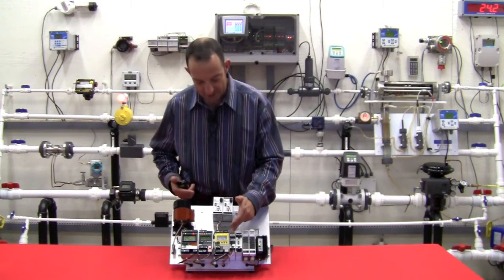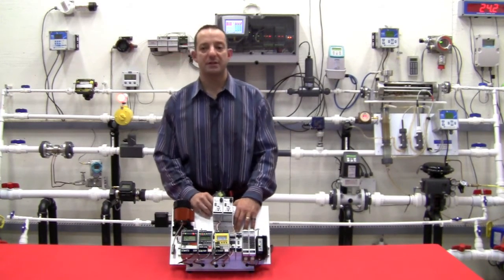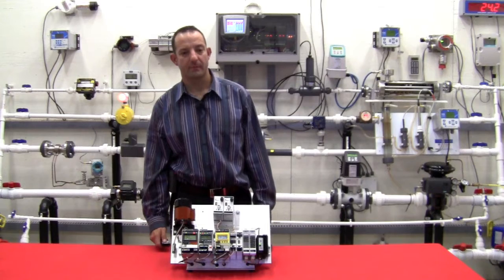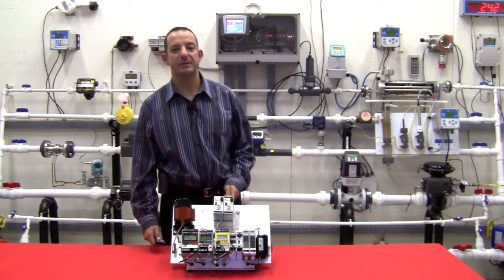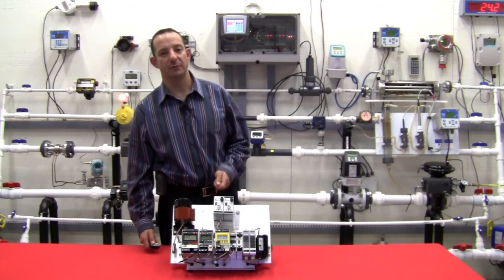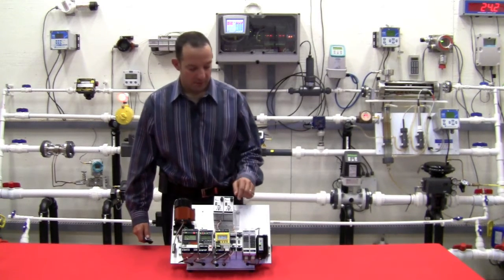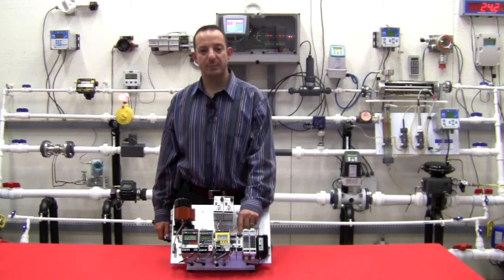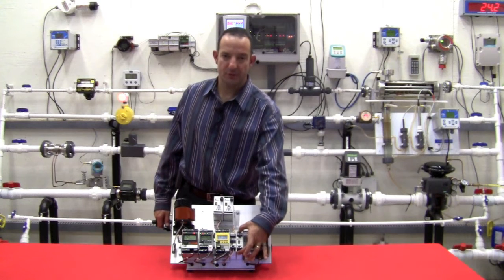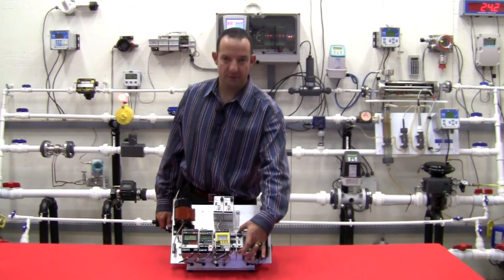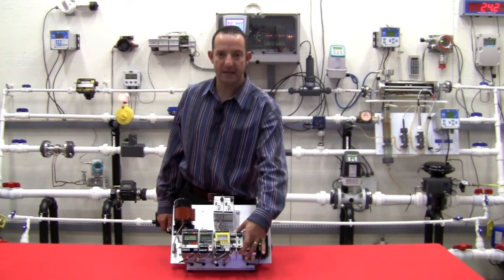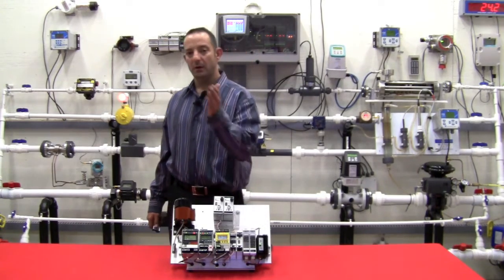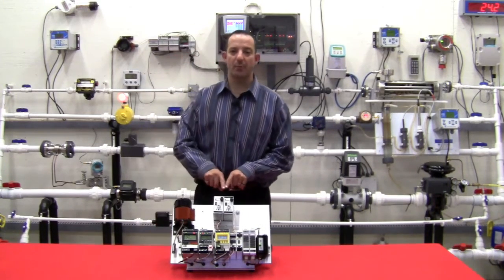In the case of our high accuracy temperature transmitters, many times the temperature transmitter is more accurate than the PLC input card. So let's go through those reasons why to use temperature transmitters instead of direct wiring. With a temperature transmitter, often we can improve accuracy greatly.